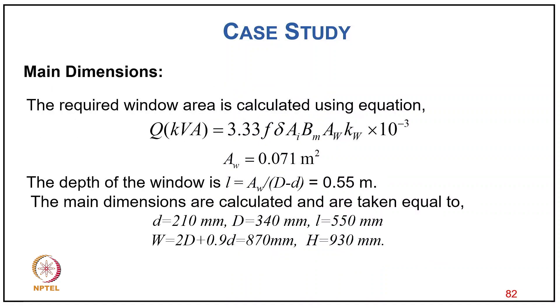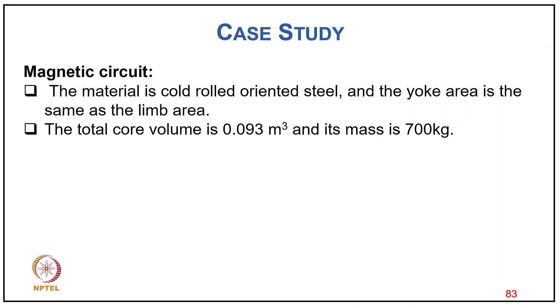Main dimensions: d = 210 mm, D = 340 mm, L = 550 mm, W = 2D + 0.9d = 870 mm, H = 930 mm. Material is cold-rolled oriented steel; yoke area same as limb area. Total core volume 0.093 m³, mass 700 kg. From the 50 Hz characteristic curve of cold-rolled vs. hot-rolled steel laminations (0.35 mm), specific loss at Bm = 1.45 T is 1.5 W/kg. Total core loss with building factor 1.3: Pi = 700 × 1.5 × 1.3 = 1.37 kW.